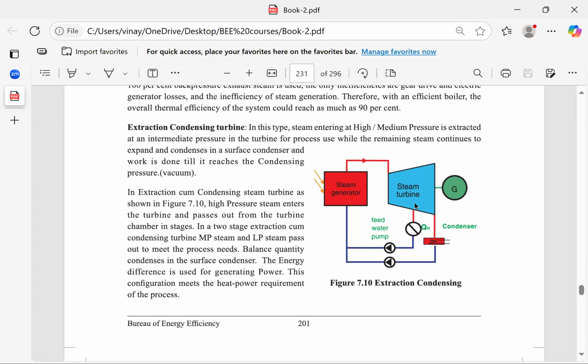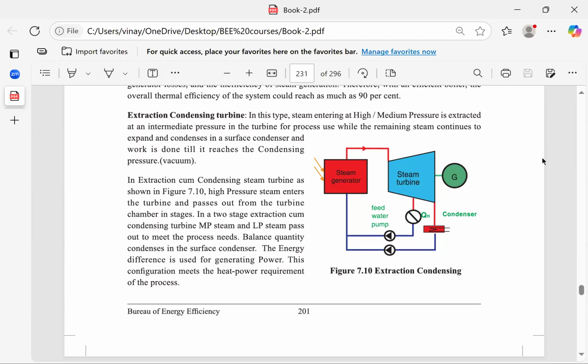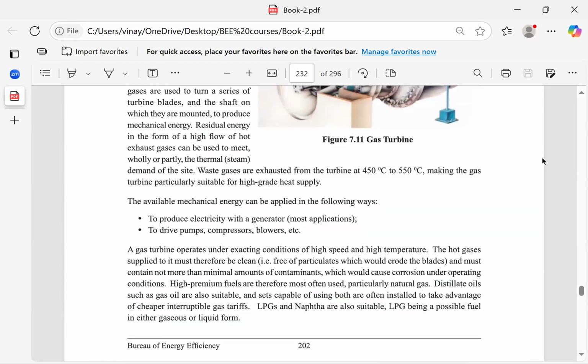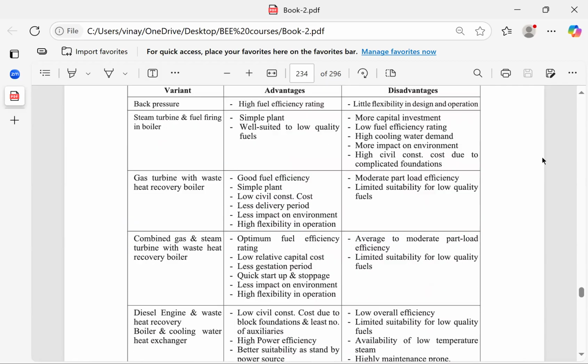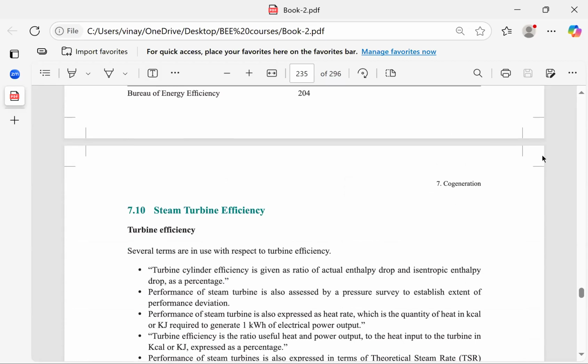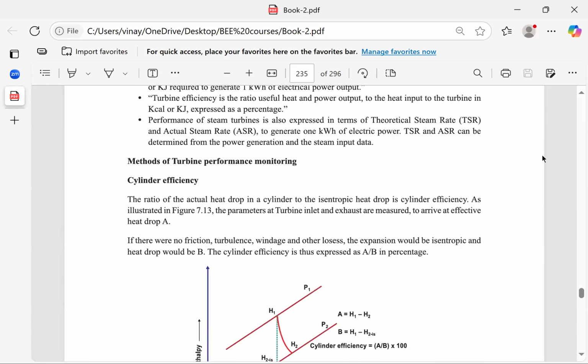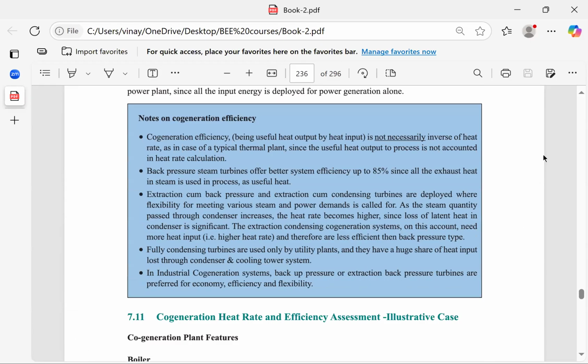At this stage you have to take a bleeding of steam to meet the process requirement. Again, if there's a 5 kg requirement, go further down and take another tapping for 5 kg. This method of measuring is known as pressure gradient or pressure survey across the turbine, which helps you find the correct pressure and temperature of steam available in that particular section.